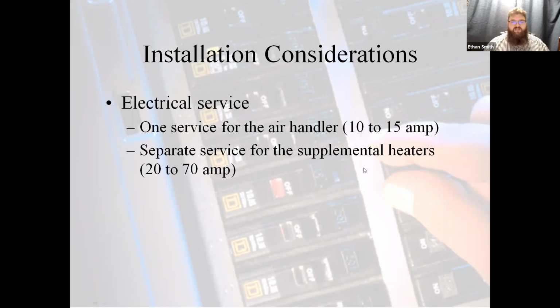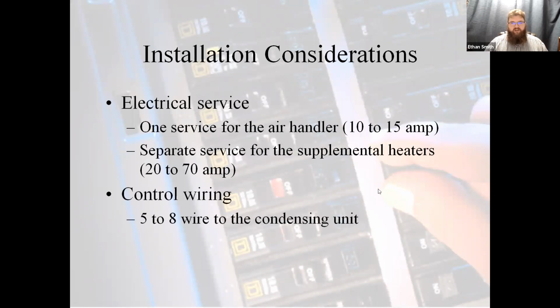So make sure that you've got enough electricity and enough services there for your application. We talked about control wires again, but make your life easy, guys. Run some 8-strand to the outdoor unit if it's not a communicating outdoor heat pump. You don't want to be running 4-strand, or even 3 strands of 4-strand, because then you've got multiple wires of the same color.